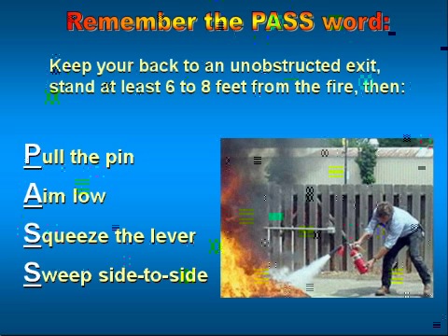Good examples here, as I said, carbon dioxide works well at 8 feet. Most of your halons or handheld fire extinguishers are talking 10 feet. ABCs are 10 feet. But that water-based fire extinguisher, if you look at the label on it, will go out to as much as 20 feet as the initial starting point to engage a fire. If you do not start at those distances or you close on the fire before you start, you're putting yourself in an unnecessary risk.